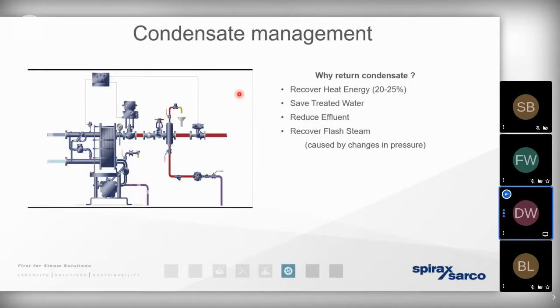There'd be a huge, huge inefficiency. And also there's a value in that liquid condensate as well. So by locking the steam in the network, we're increasing the overall efficiency of the distribution network. But by allowing the condensate to drain away and get it recovered back to the boiler house, we can reuse all of that heat energy that is present within the liquid condensate.